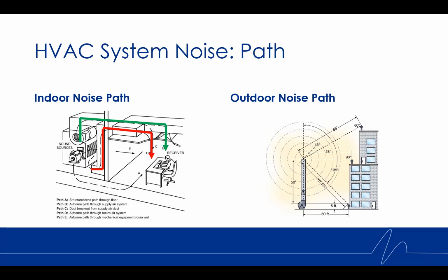What's also going to affect it is at what angle you are relative to that sound source. So if you look at this exhaust fan stack I have on the image on the right here, you can likely see that if you were standing right at the very end of that exhaust stack, you're going to be experiencing a lot more noise than if you're standing on the ground right next to the building. So these are the things within the path that we're going to be considering when looking at an outdoor or environmental noise problem.